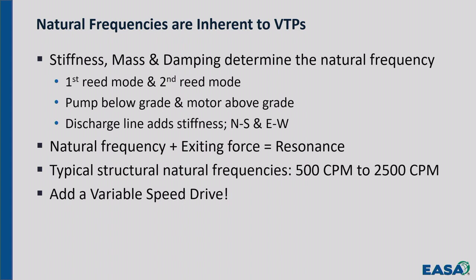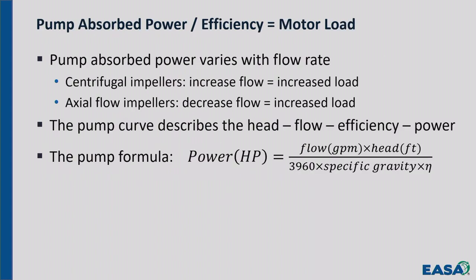Okay. Another problem we run across is you put the motor on, it pulls high current. And it doesn't make a difference what was done with the pump. If you fix the motor, and there's high current, the customer says it's a motor problem. They could have a pump in terrible condition. They could have put a new pump in and replaced it. They could have changed impellers. They could have changed the system, valve configurations, and done all sorts of things that could have caused high motor current.